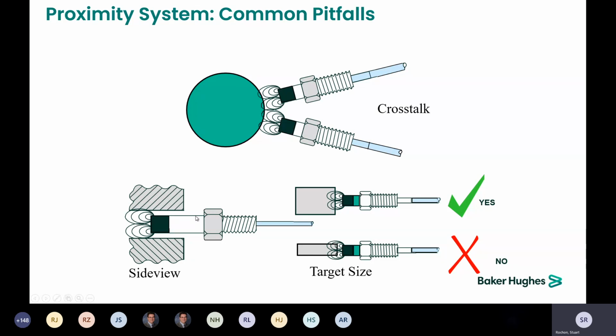One of the ways you can do that is to use a plastic, copper, or bronze rod, insert it into the hole, see where the shaft is, measure that on the probe, put yourself a little mark, and then roll it in to no more than that depth. Also, monitoring the DC component of the signal from the proximeter with a meter, rolling it down to -2 volts. You can't get to -2 volts with side view. So if you get to -2 volts, you know that you're looking at the shaft, and then you can back it out to your -10.